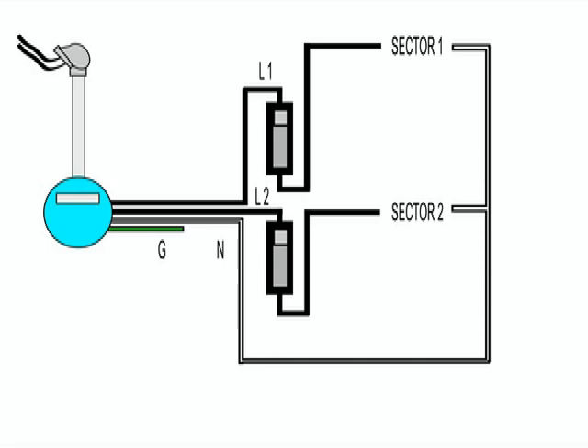Here, each of the two phases or live cables can be connected to a different sector of the building. For example, the rooms located at the right side can be connected to a thermal switch coming from phase L1, and the rooms at the left side can be connected to another thermal switch fed by phase L2.